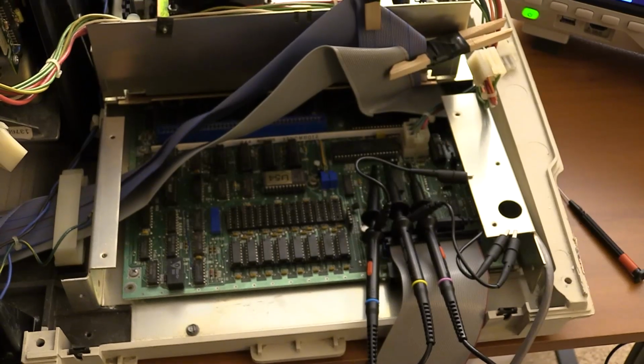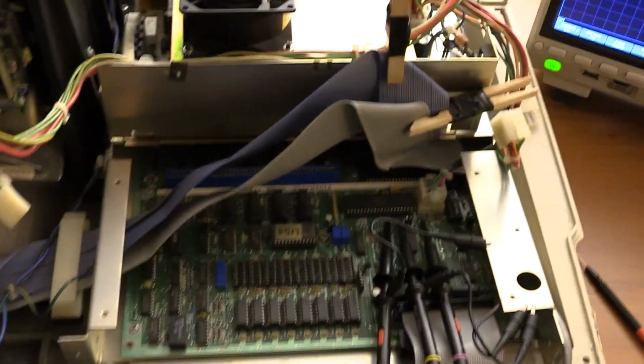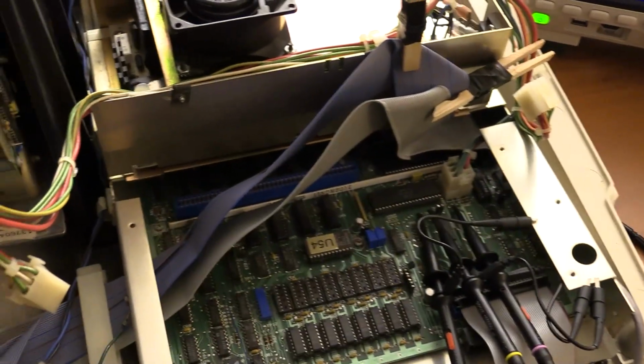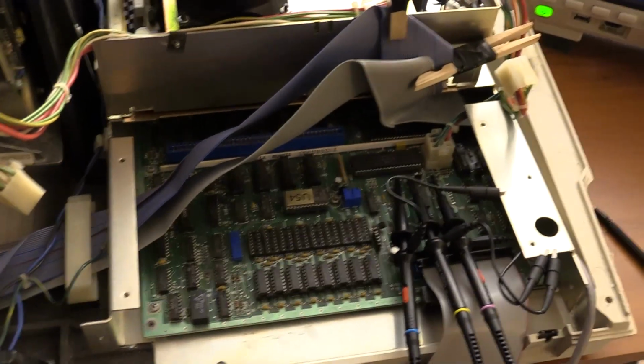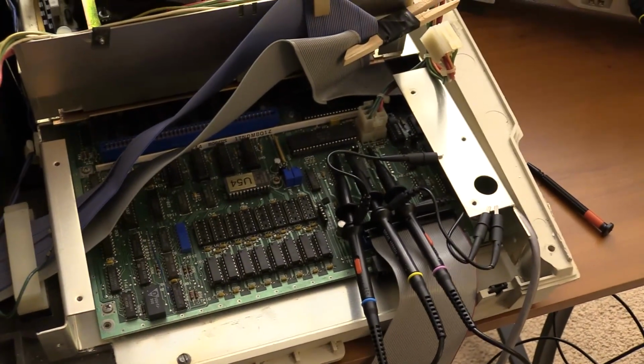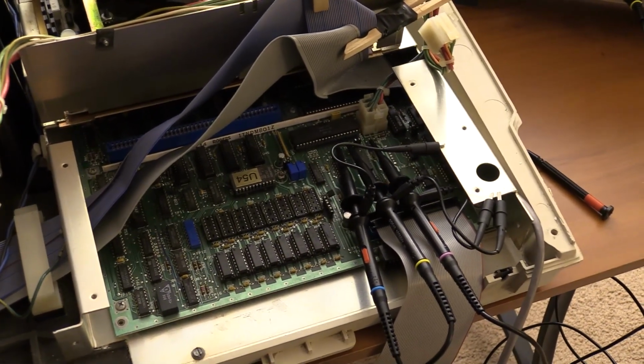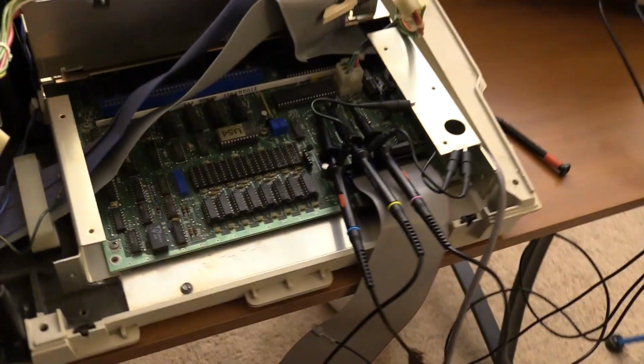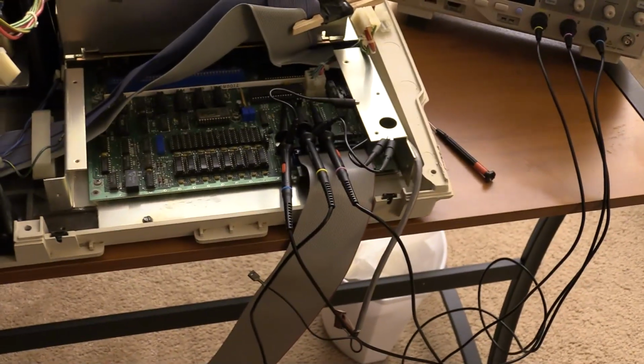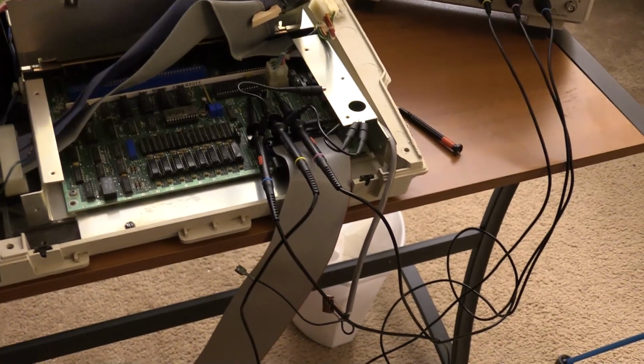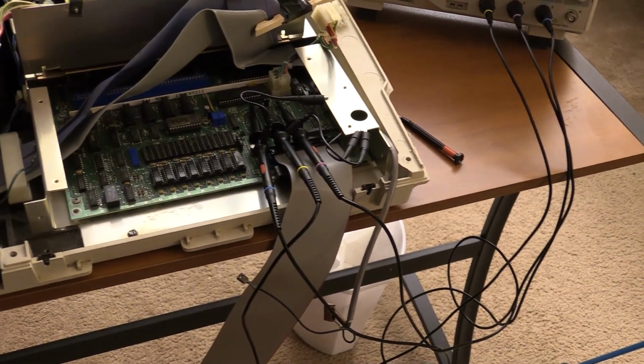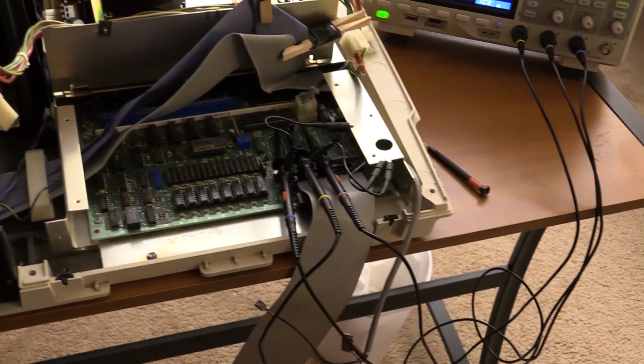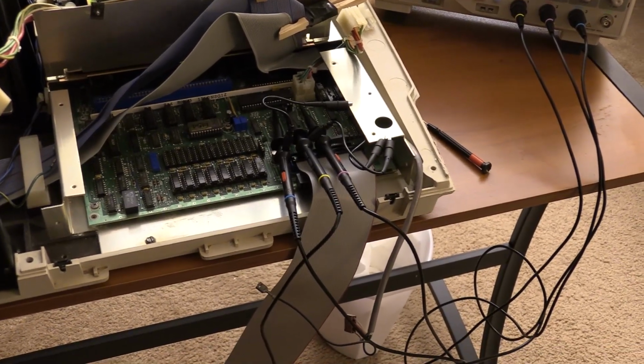The instructions take great care to mention that for one of these adjustments, the machine has to be on and measured either within the first 60 seconds or it has to wait at least 8 minutes. And you'll get different answers if you don't. So I think what we're going to try and do is see if I can get that one measured up quickly. That's going to be channel 1, I believe, is TP9, right? Did I do that? I did.